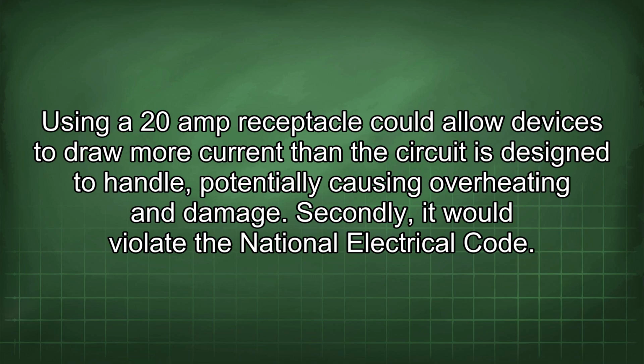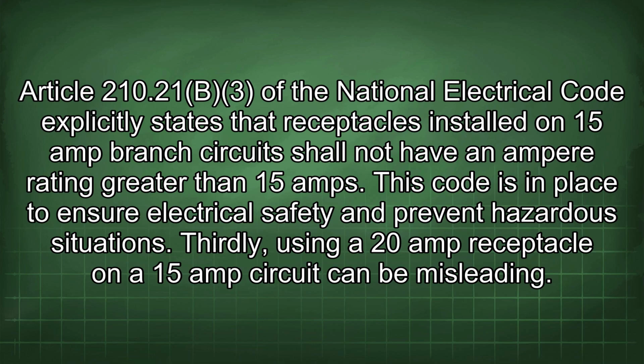causing overheating and damage. Secondly, it would violate the National Electrical Code. Article 210.21(B)(3) of the National Electrical Code explicitly states that receptacles installed on 15 amp branch circuits shall not have an ampere rating greater than 15 amps. This code is in place to ensure electrical safety and prevent hazardous situations.